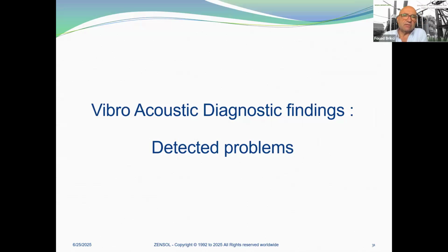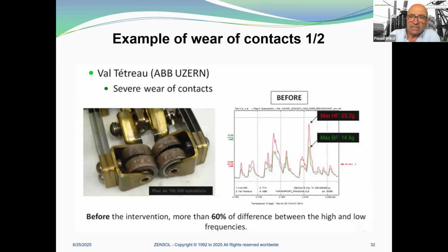Vibroacoustic diagnostic findings. Here you have some examples of detected problems. This one is simple. This is a typical case where the high frequency and low frequency comparison give good information on the degree of wear of contacts. This is severe contact wear; here you have the picture of the mechanism. Before the intervention, there was more than 60% difference between the high and low frequency. The high frequency is in red and the low frequency is in green.